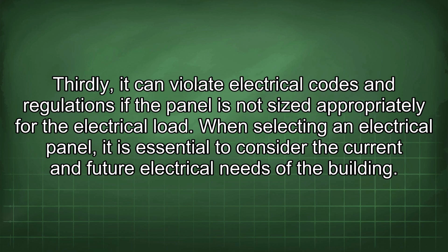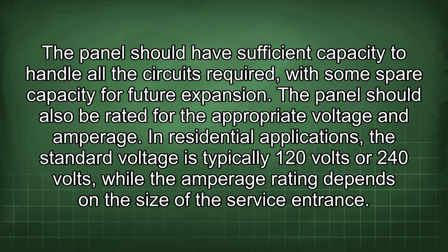When selecting an electrical panel, it is essential to consider the current and future electrical needs of the building. The panel should have sufficient capacity to handle all the circuits required, with some spare capacity for future expansion. The panel should also be rated for the appropriate voltage and amperage. In residential applications, the standard voltage is typically 120 volts or 240 volts, while the amperage rating depends on the size of the service entrance.